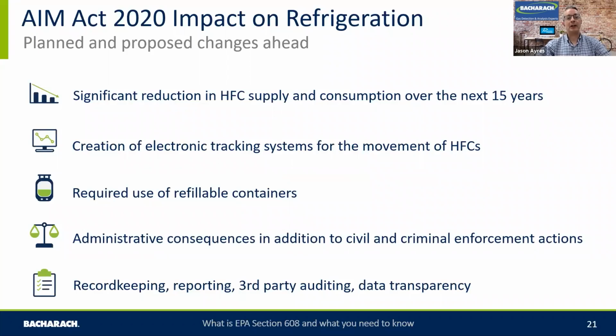So what does this impact mean on refrigeration? Well, there's going to be a reduction in HFC supply and consumption over the next 15 years. Understand that, be aware of that. There'll be more tracking systems, electronic and reporting requirements for the movement of HFCs. And this could be from their production, the tracking of the cylinder, and the tracking of that gas throughout its life cycle of where it goes into the system.